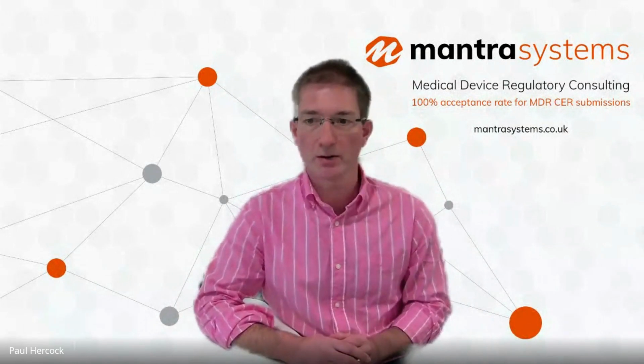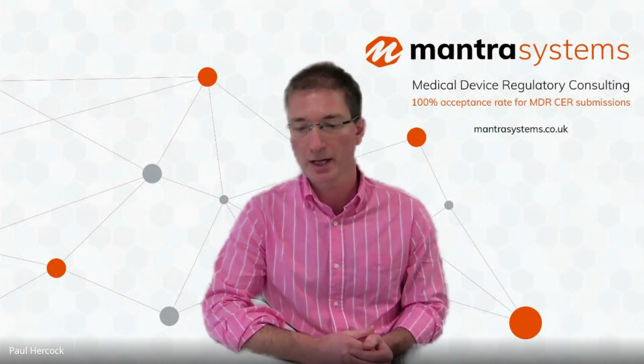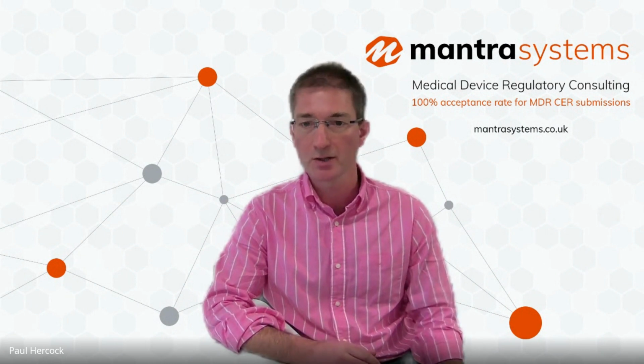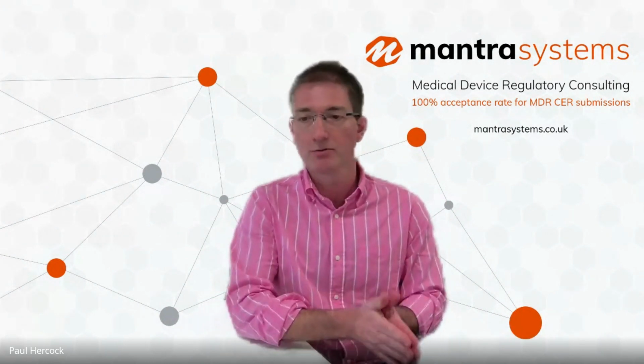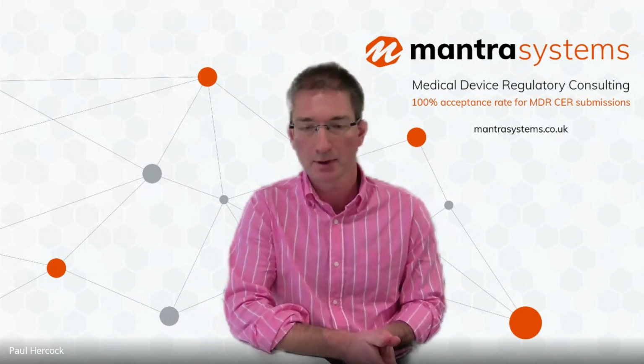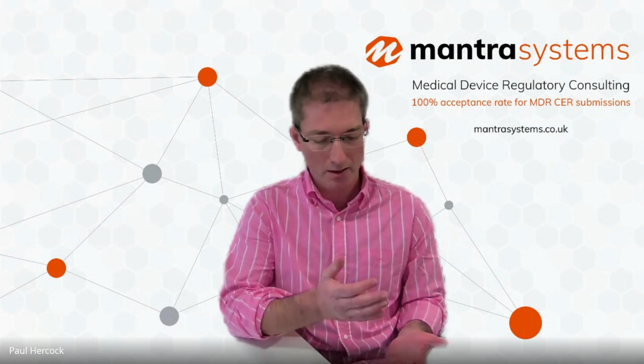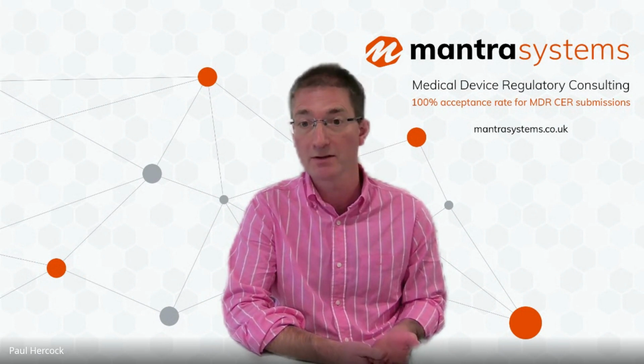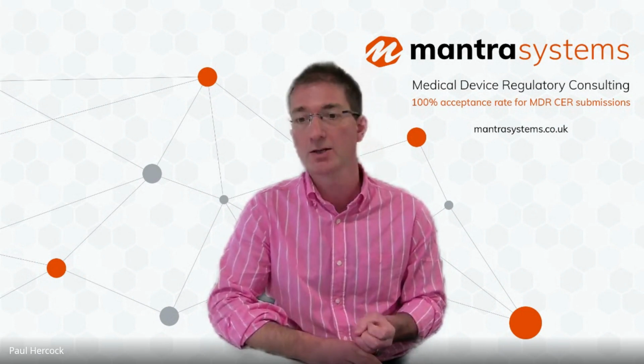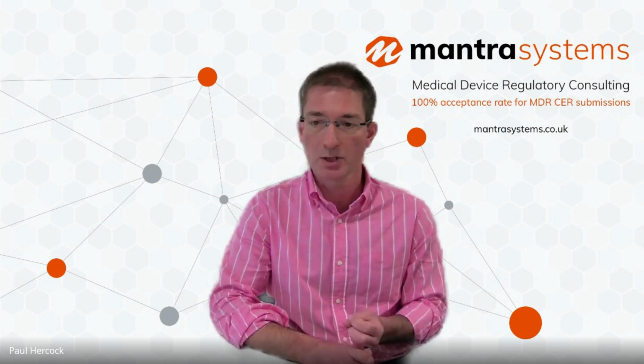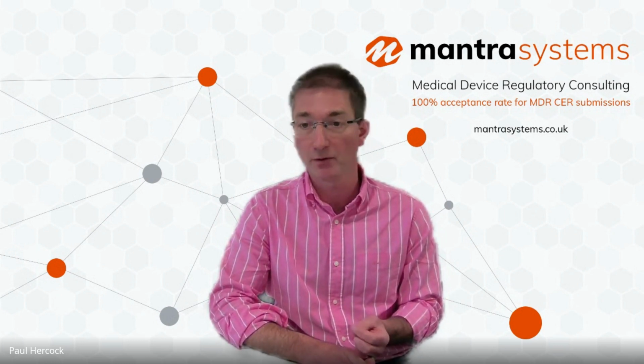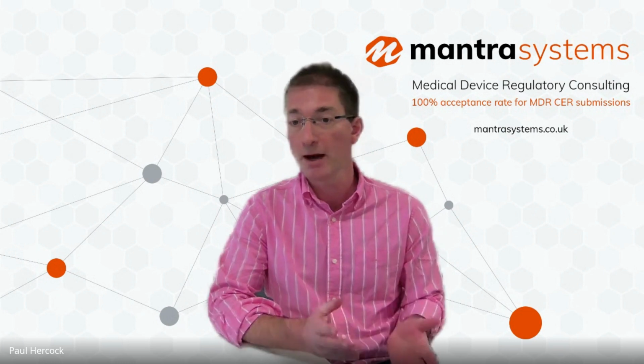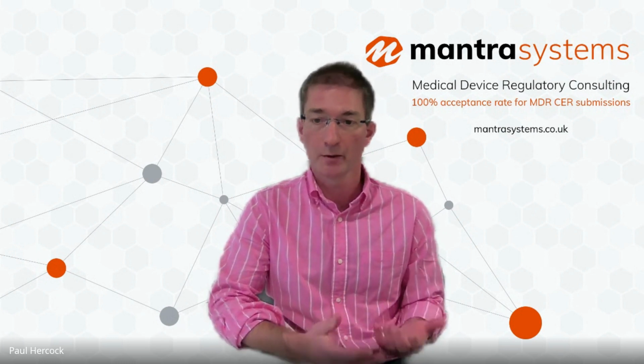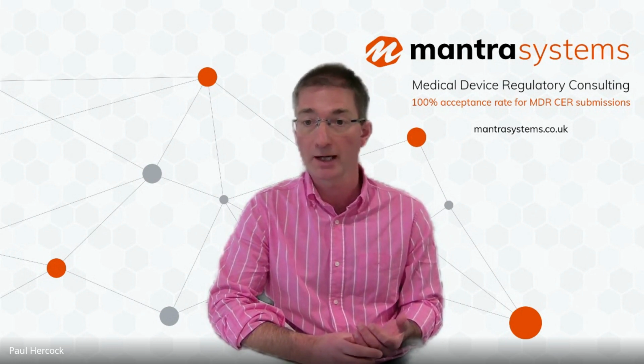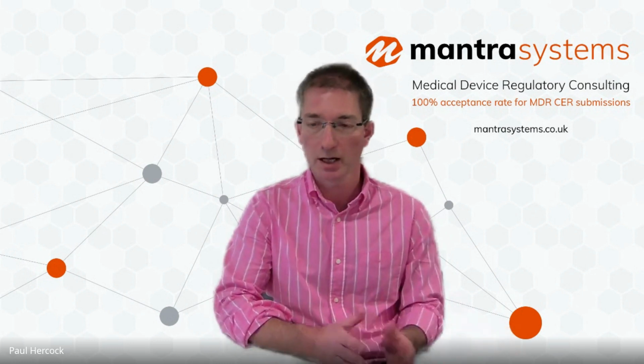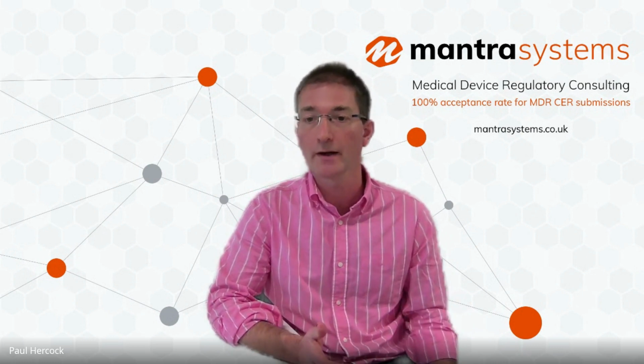So software versus hardware. Obviously, there are fundamental differences in the way that the device presents itself to the user. But the bottom line is that the fundamentals of writing a clinical evaluation are the same. It's still necessary to meet the basic requirements in terms of the objectives of a clinical evaluation. So demonstrating suitability for intended purpose, demonstrating conformity with the relevant general safety and performance requirements, demonstrating that the benefit-risk profile is acceptable, and that the product performs in line with safety and performance objectives. So they don't change, and in the vast majority of cases, they would still rely on clinical evidence.